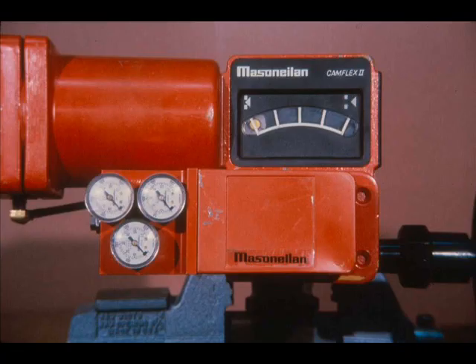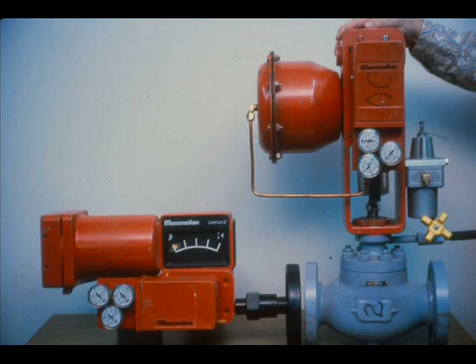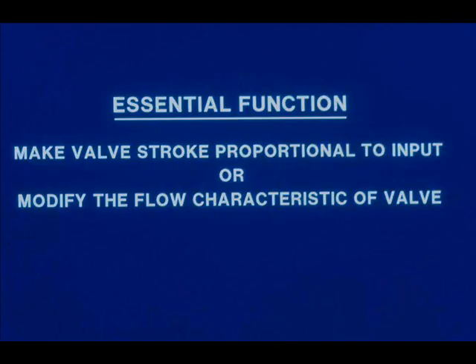The Masoneilan Model 4600 pneumatic valve positioner design is based on the force balance principle. The input signal pressure is opposed by a feedback spring. The 4600 positioner is used with the Camflex II valve and the Sigma-F actuator. The essential function of the positioner is to make the valve stroke proportional to the input signal from a controller, or to modify the natural flow characteristic of the valve itself through the use of a cam.